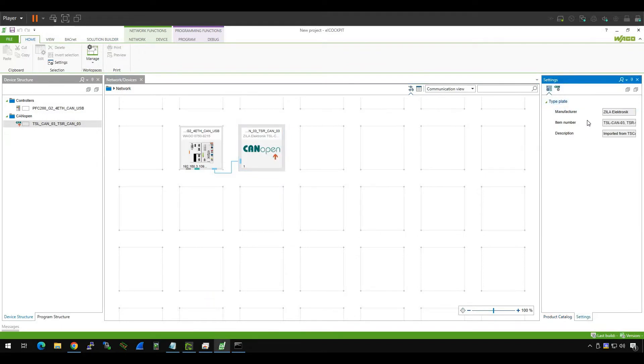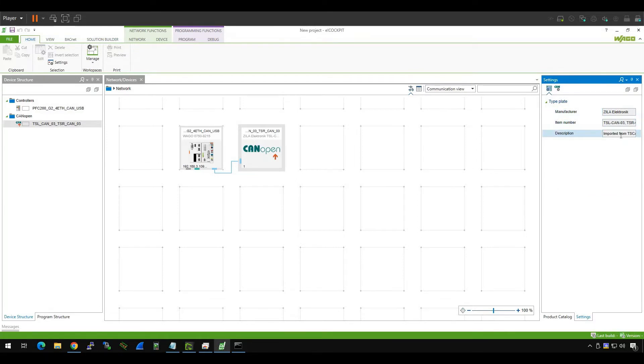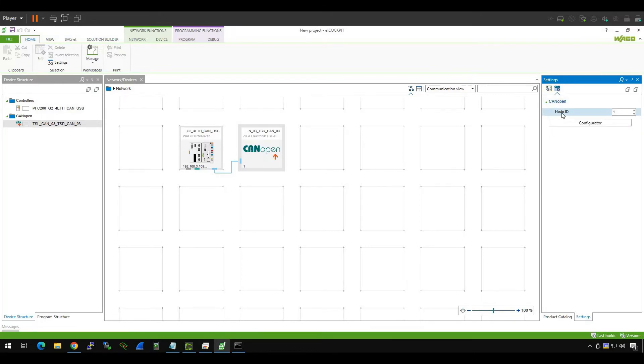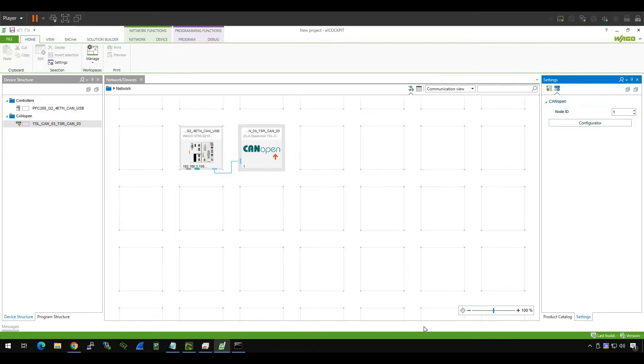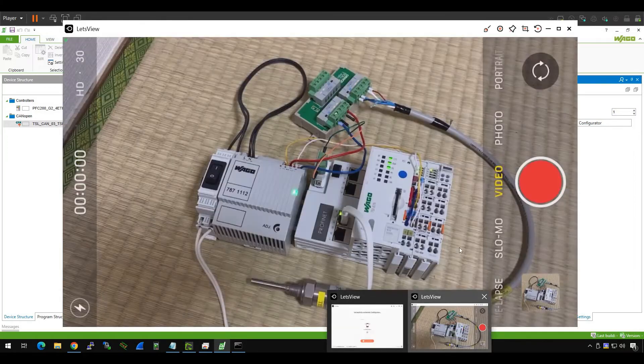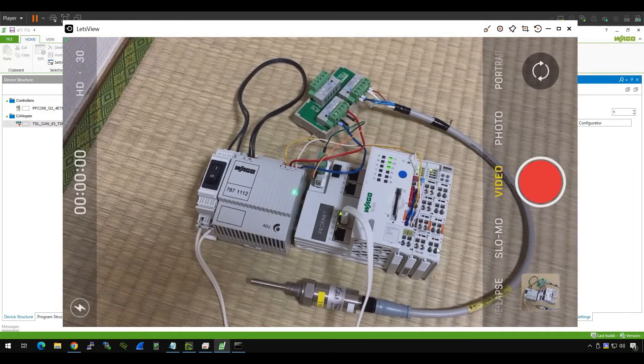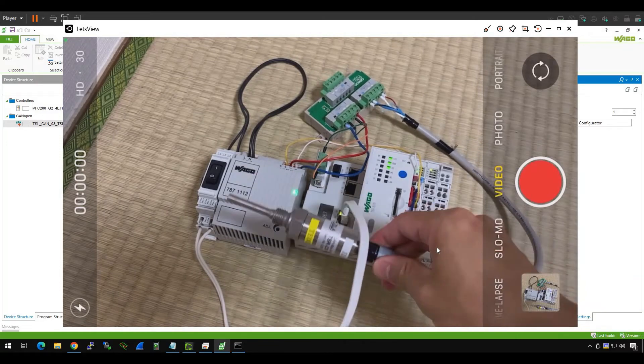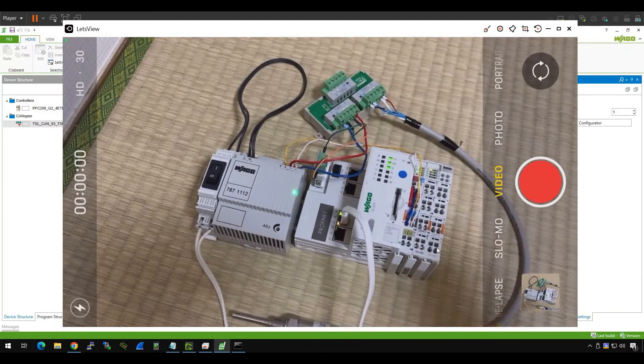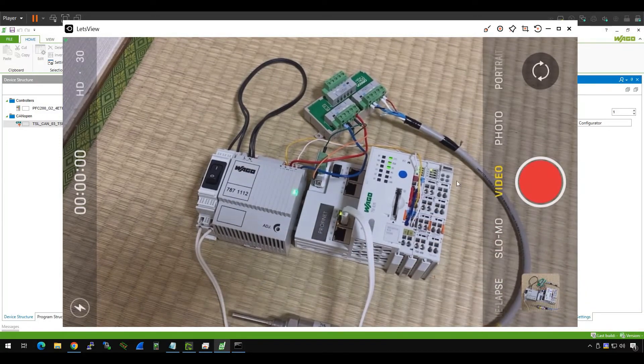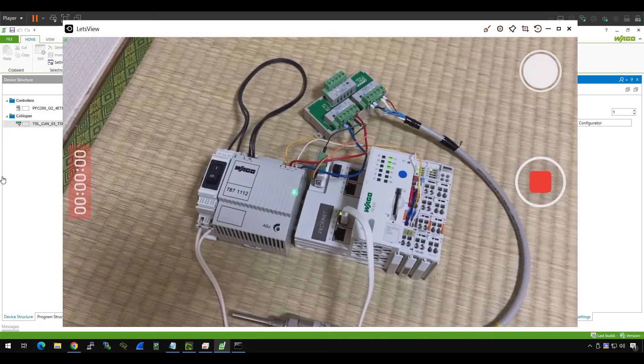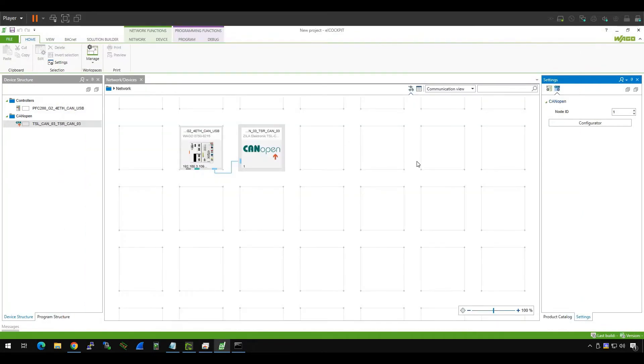And then in this step, you can see where this sensor comes from, its item number and descriptions. But this is not what I need to care about. And then click the CANopen interface, CANopen settings. Here is a node ID. You need to set exactly what your sensor is. So in my case, it is 25. So in here, I need to set the node ID same as here. It's 25. Just finish. Okay. The slave side is finished.